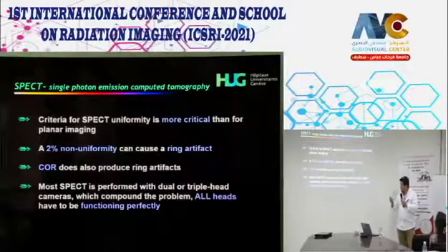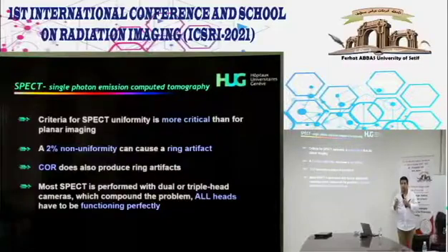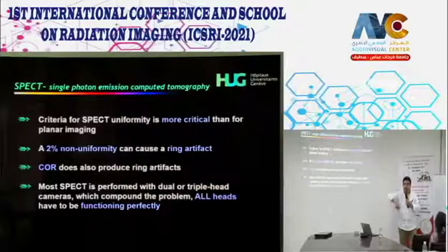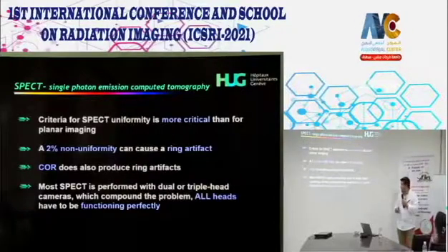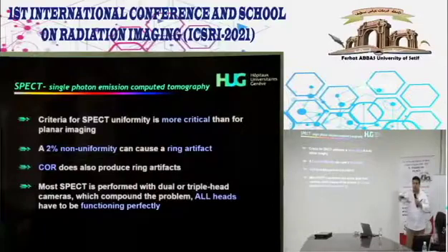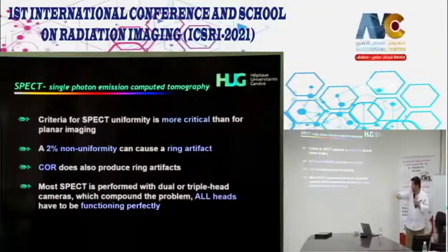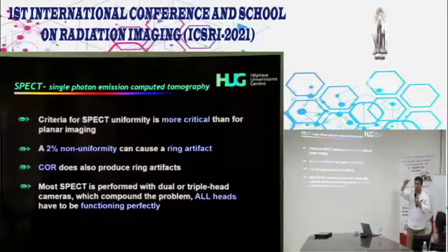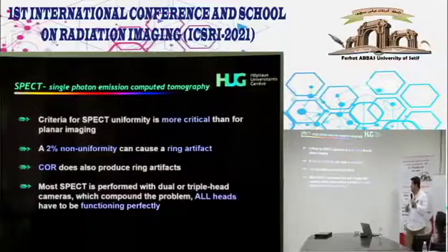But what's important to mention here is what we call the non-uniformities, because the sodium iodide detector has a very large surface, 40 by 50 or 30 by 50 centimeters. And you've got some non-uniformities. For instance, the uniformity changes depending on where you are within the field of view, because it's also linked to the gains of the PMTs.